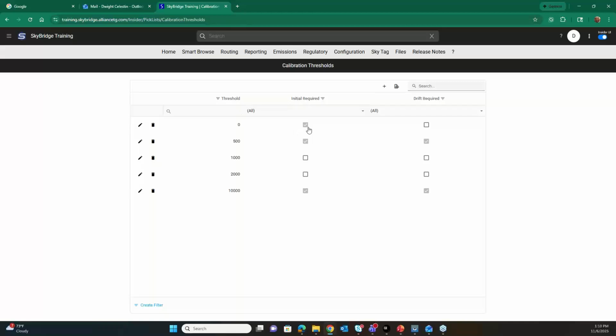Okay. Because the precision, the method 21 precision calibration, you only use 0 to stabilize your gases here, to introduce your 0 to get it down to 0, and then hit it with the span gas, 500, 10,000, 2,000, or 1,000, whatever the case may be.